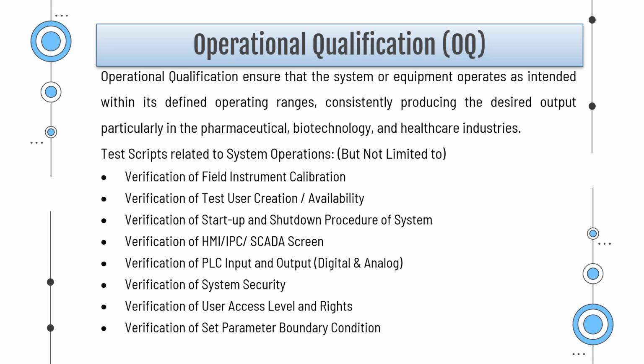Verification of test user creation availability. Verification of startup and shutdown procedure of system. Verification of HMI, IPC, SCADA screen. Verification of PLC input and output, digital and analog. Verification of system security. Verification of user access level and rights.